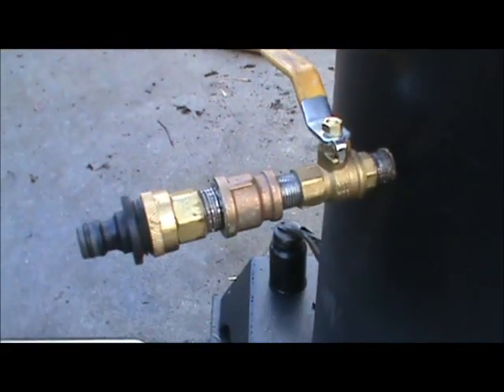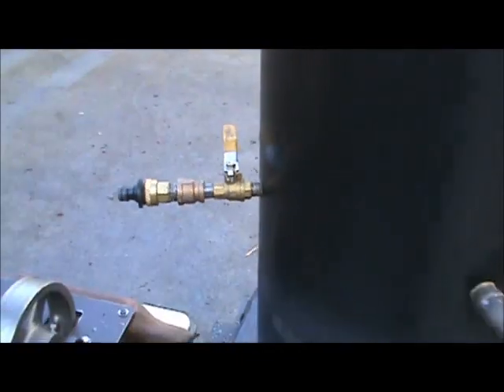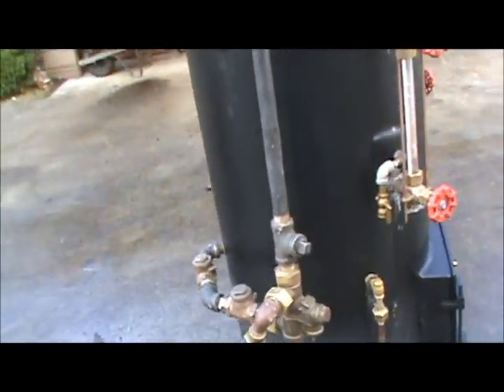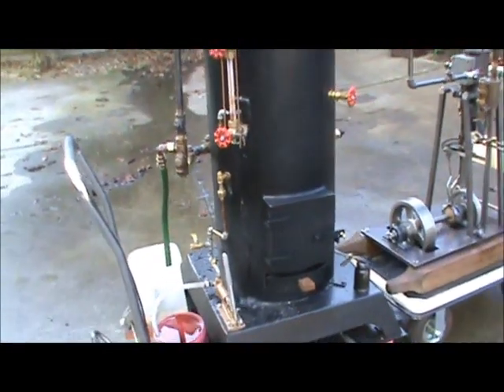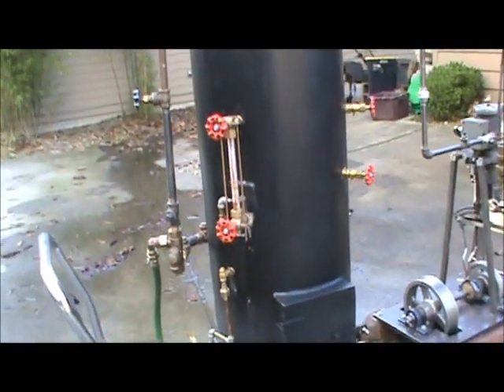There's an adapter here — right here — you can plug a hose on there and put water into it once the boiler pressure is down really low, if you want to get water into it slowly. The hand pump works very well too — no problem there, it's a good way to get water into it.